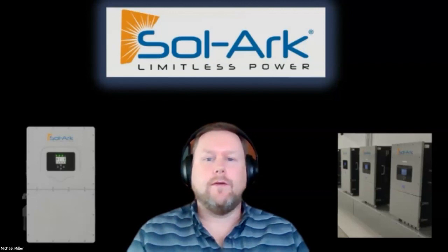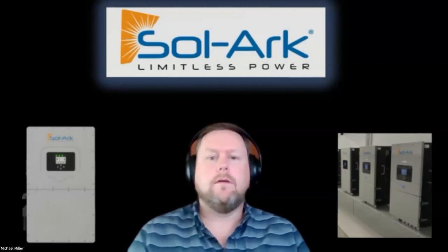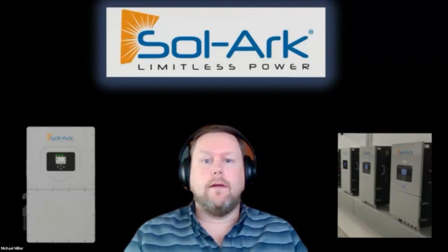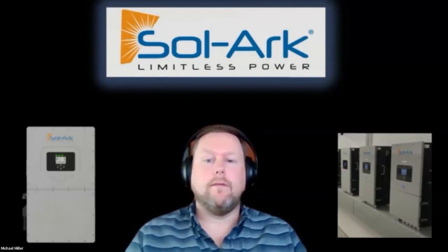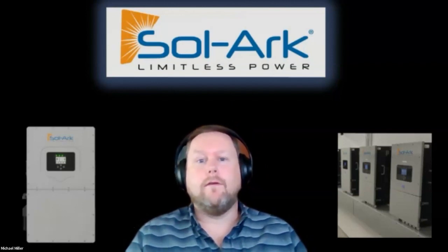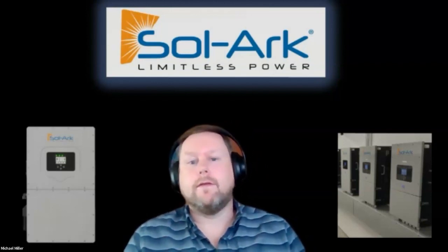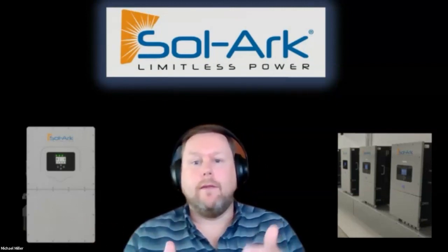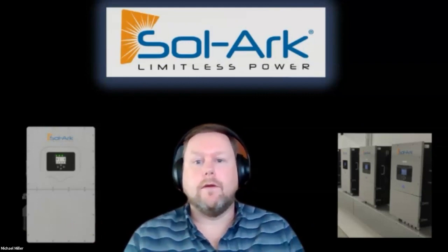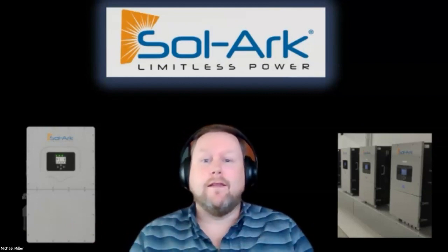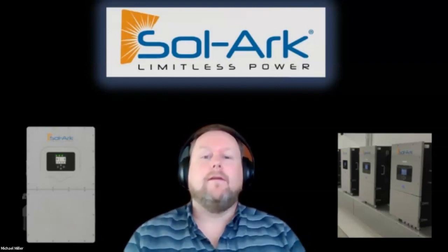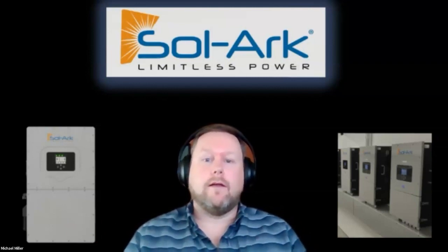That's pretty much it. We do have diagrams in the manual that show this, so that's the way I've done it in the past with the 200 amp. If you're doing breaker feed, you could just have your backed-up panel. Say it's a 12K, for example, you could have an interlock switch or interlock breaker in your essential loads panel that could be fed from either the grid or the backed-up solar. It's important that you do not connect the load and the grid together. That's in the manual, but it's very important that those get installed correctly.